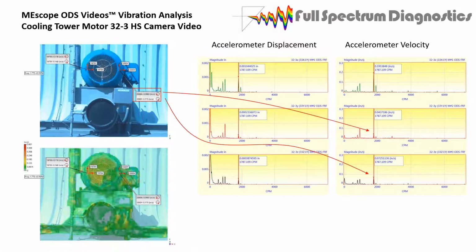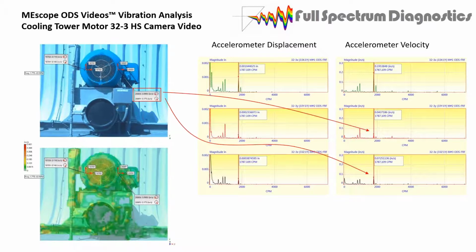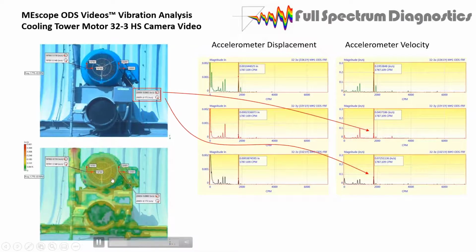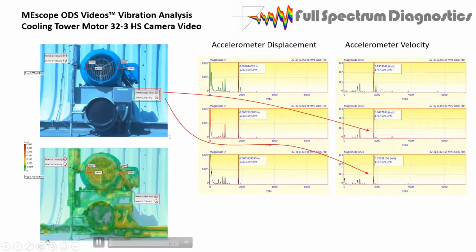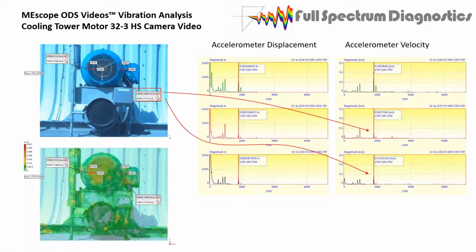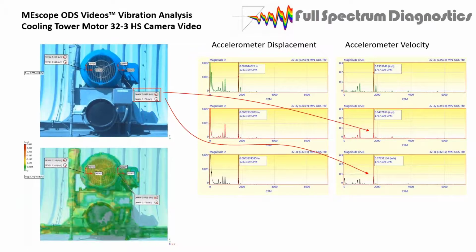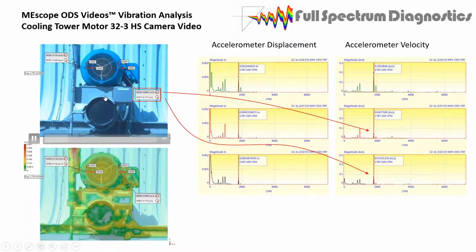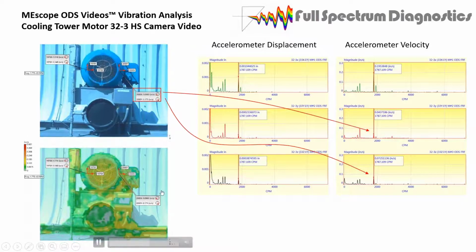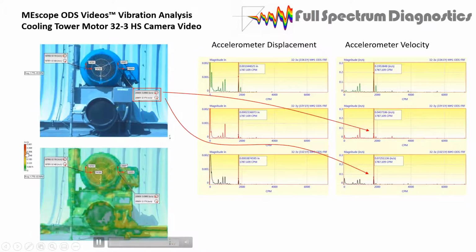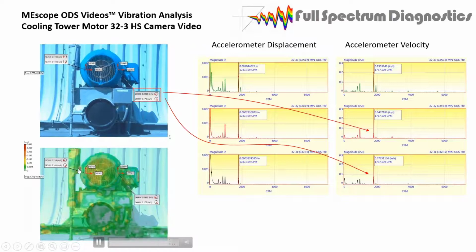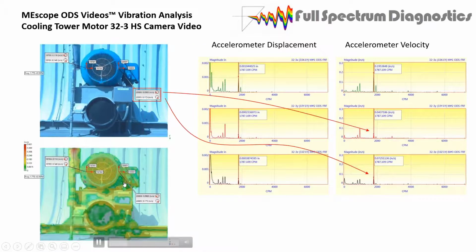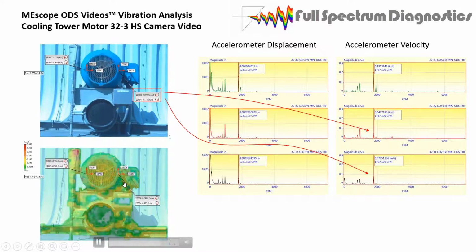This is the front view with the background taken away, and I have some color contour plots here, so you can kind of see how the machine's ovalizing or whirling a little bit and twisting. And you can see the amplitudes right in here. There was a little oil aerator or something in here that was moving back and forth. So good deal.